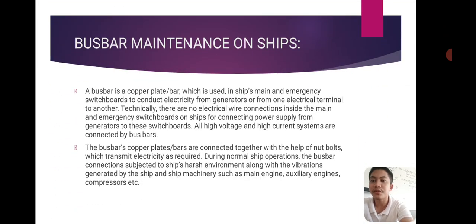Bus bar maintenance on ship. A bus bar is a copper plate or bar which is used in the ship's main and emergency switchboard to conduct electricity from generators or from one electrical terminal to another. Technically, there are no electrical wire connections inside the main and emergency switchboard on a ship for connecting power supply from generators to this switchboard. All high voltage and high current systems are connected by bus bars.